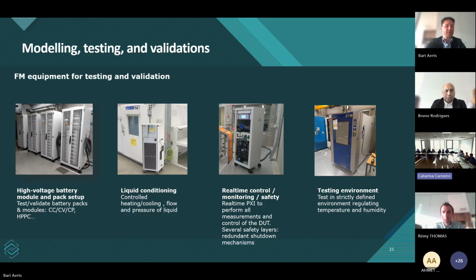Then we have the real-time control monitoring safety setup. This is a real-time PXI system to perform all the measurements and control of the device under test. Especially important here is that we have several safety layers, including a redundant shutdown mechanism that can be used in case something goes wrong. The BMS itself communicates not only with this setup, but also with all the other devices like the module tester and the conditioning system, so that if something goes wrong, all those devices can shut down the systems.